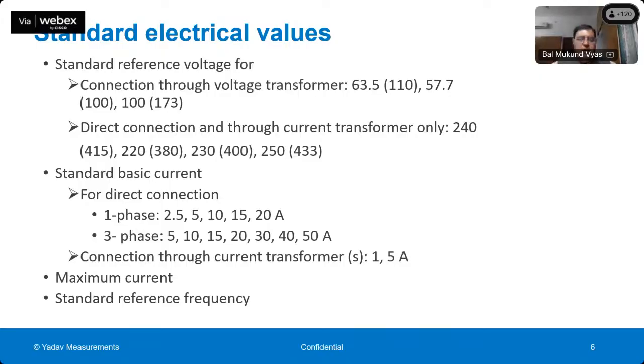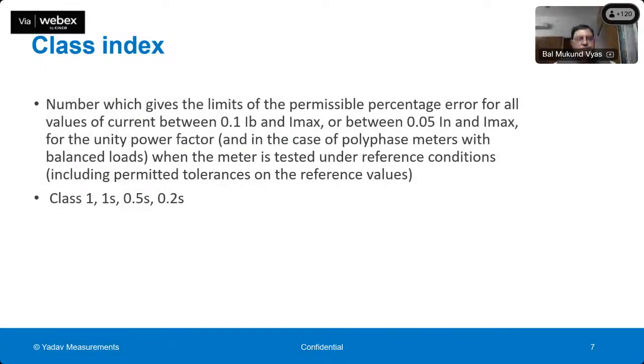Similarly, the current ratings are specified. For direct connection, the current ratings are specified from 2.5 ampere to 50 ampere, and if connection is through a current transformer, then it is only 1 ampere and 5 ampere, because this is what the secondary of current transformers gives. Another very important requirement which has to be specified on an electricity meter is maximum current. Maximum current is the value of the current which the meter will withstand, and also work accurately. Beyond maximum current, the meter might be inaccurate, and it might get damaged. And of course, the reference frequency has to be specified.